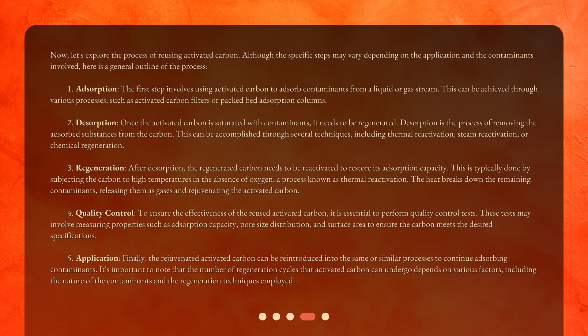Step three — regeneration: after desorption, the regenerated carbon needs to be reactivated to restore its adsorption capacity. This is typically done by subjecting the carbon to high temperatures in the absence of oxygen, a process known as thermal reactivation. The heat breaks down the remaining contaminants, releasing them as gases and rejuvenating the activated carbon.